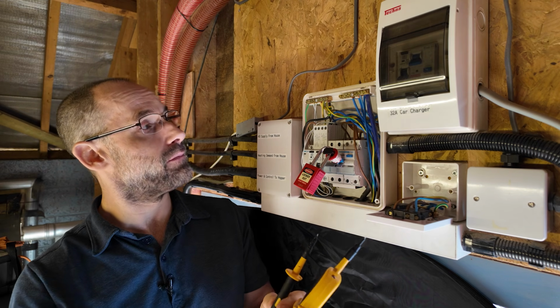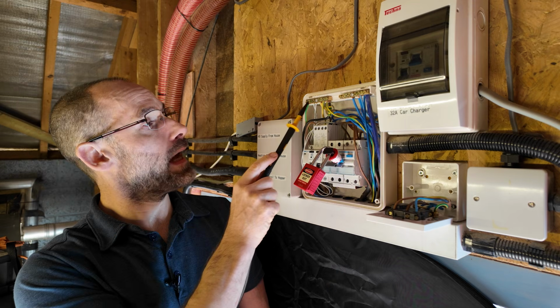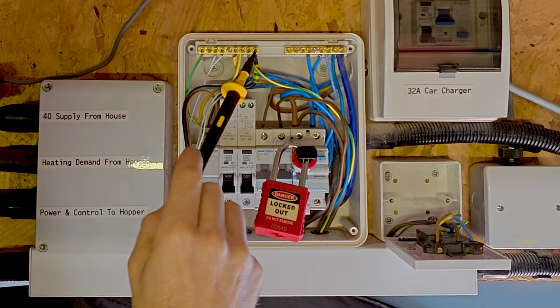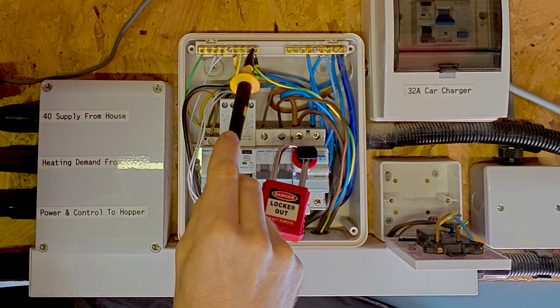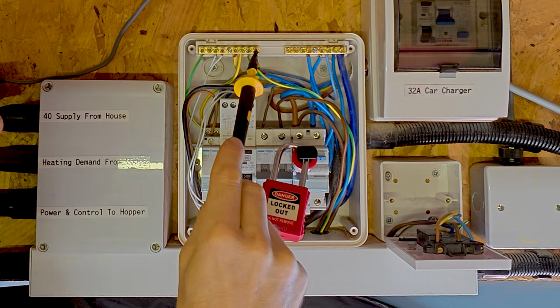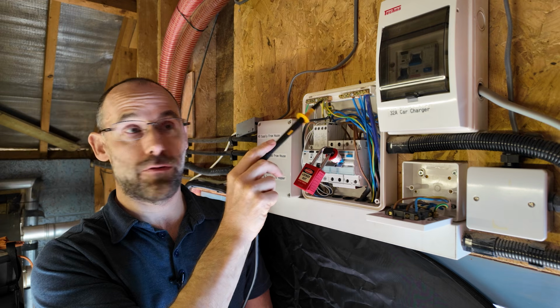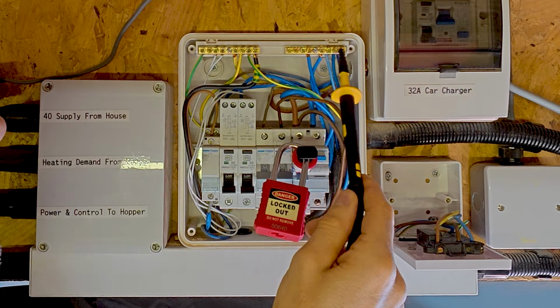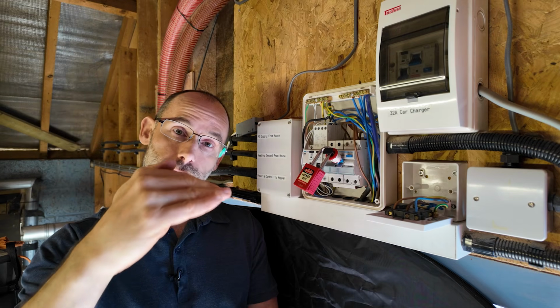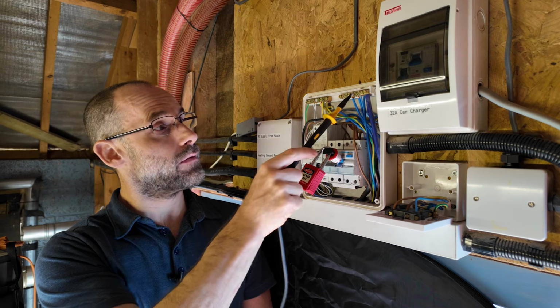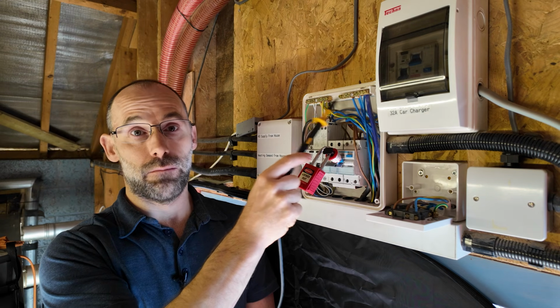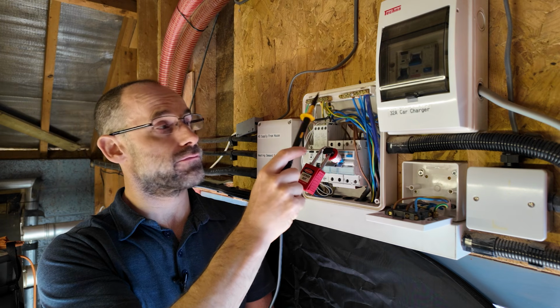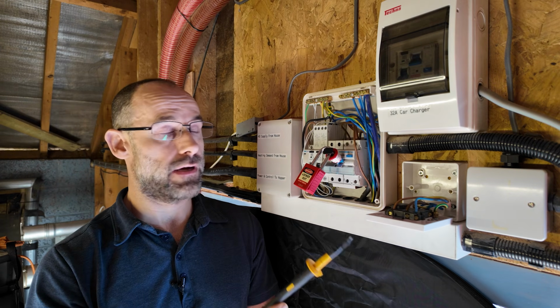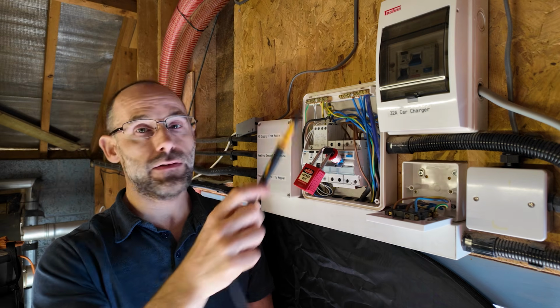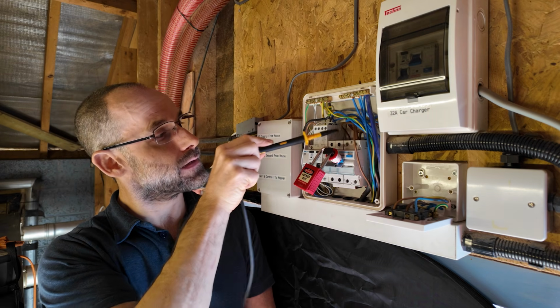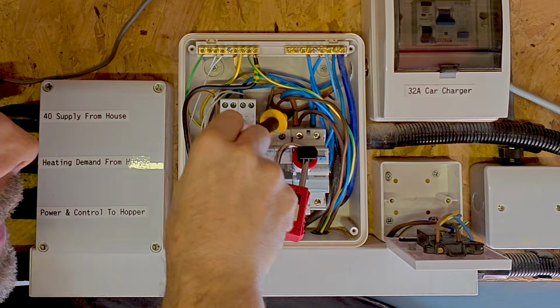So coming into this board, we have three major things. We have the CPC or earth supply coming in here from this thickest cable. This is a protective conductor that makes sure that if there is an earth fault, the current goes through this wire, not through a human being. We have the neutral, which is the 0 volt reference point for the circuit. It's basically at the same potential as earth in my particular earthing arrangement. Another thing electricians need to consider is what your earthing arrangement is, but we're not going into that in this video. So that's your neutral point, right? And then you have your line conductor coming in here. This big brown puppy there.